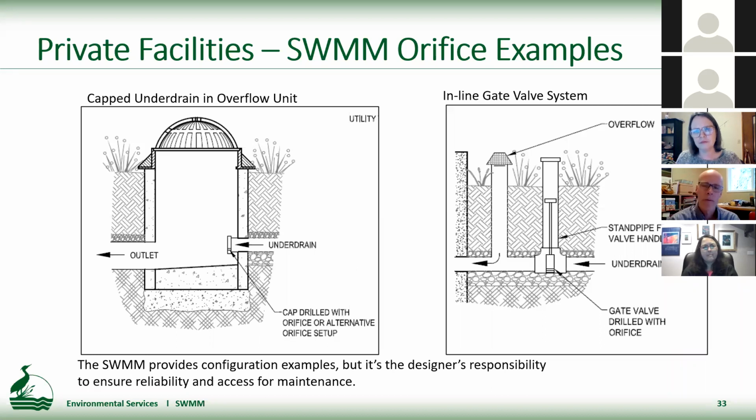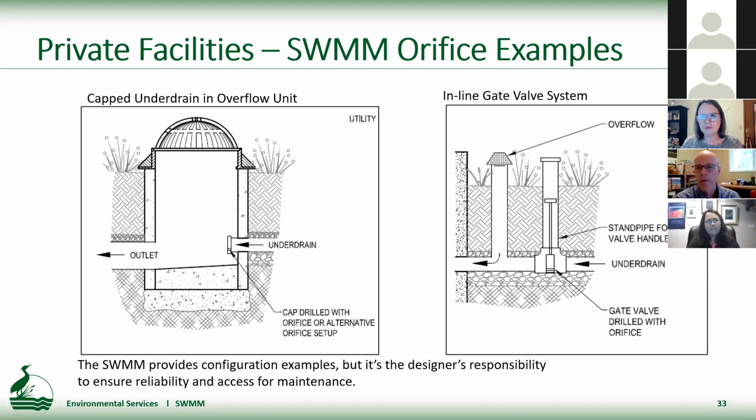The image on the right there is an approach we're not sure about yet, but it has been used, as I said, in Wilsonville here in Oregon, also in Omaha, where there's a gate valve with a drilled orifice in it that's housed in a standpipe. And I hope that we're going to see the development of a bunch of new approaches for smaller systems that don't require a beehive, but nonetheless allow accessibility.